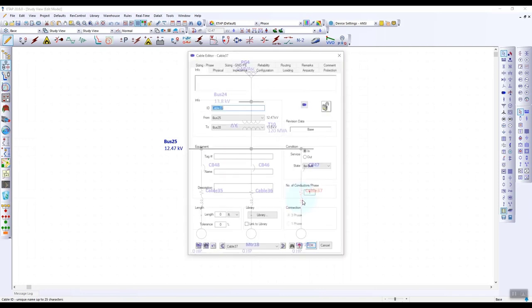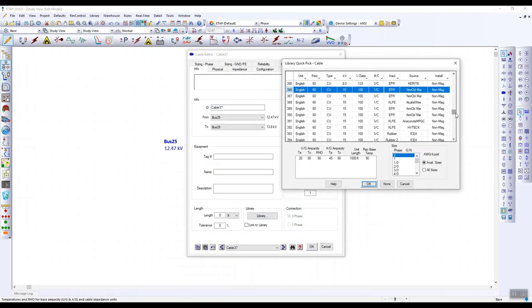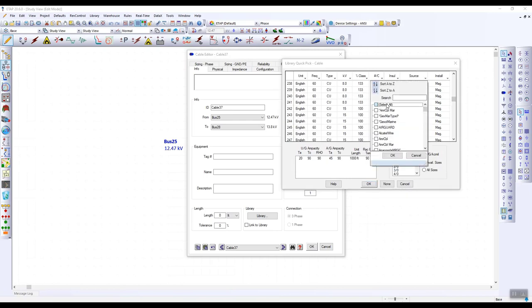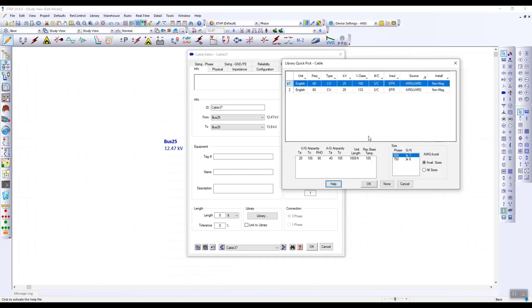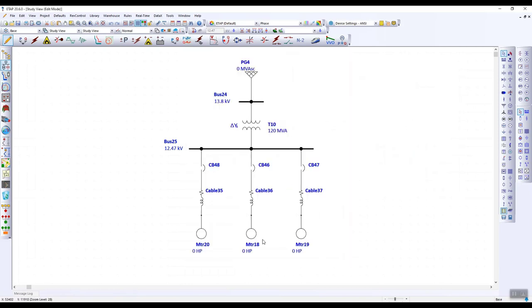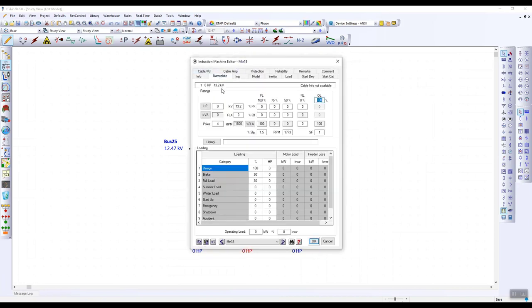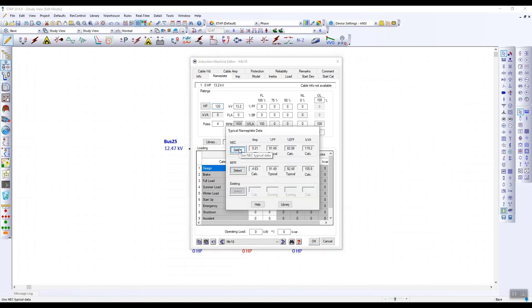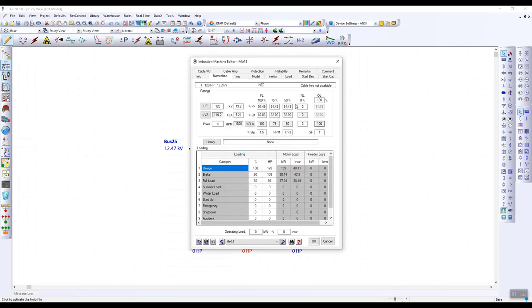Now going into the cable, we open up our cable library. So we have a huge list that you can choose from. So the cables are based on the frequency, type, voltage, class, and more. And say if we wanted to sort based on just the source, say we're looking for an air guard cable, then we can further narrow down the cable library to just the source with air guard. Now going into the motor, I'm going to go into the nameplate information. So we can start filling in the data, but say if we don't have the additional information here, then we can then select the typical nameplate data, and this table will update accordingly.